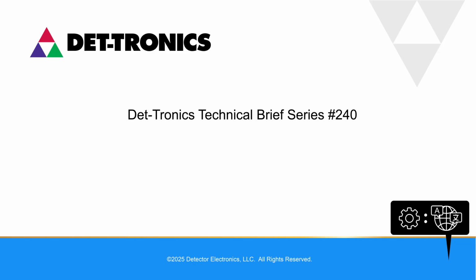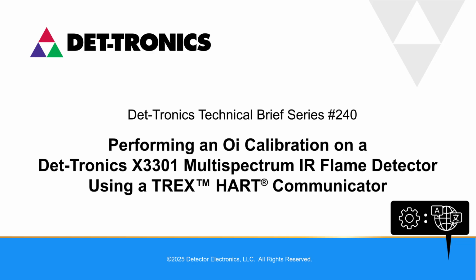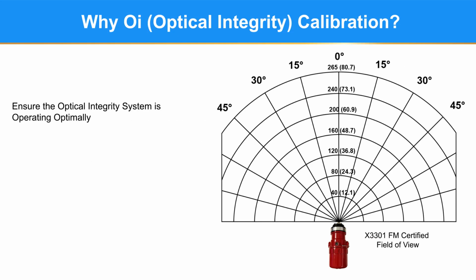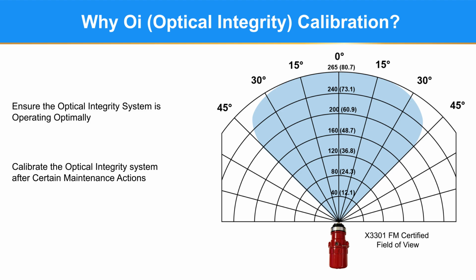Welcome to Det-Tronics Tech Brief number 240, performing an optical integrity or OI calibration on the Det-Tronics X3301 multi-spectrum IR flame detector using a TREX HART communicator. The reasons for calibrating a Det-Tronics flame detector are to ensure the optical integrity system, which automatically tests the ability of the detector to see a flame at its published range, is operating optimally, and after certain maintenance actions.